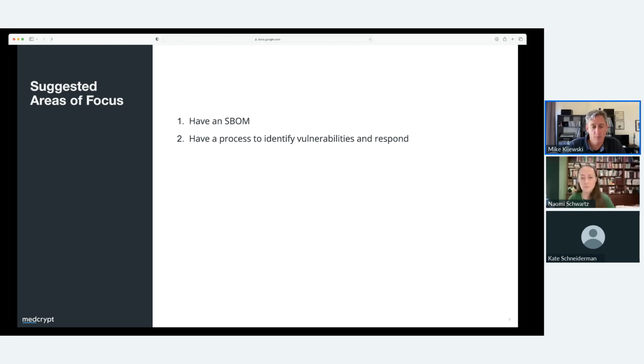You should do that. But you also need a process by which, if a new vulnerability is found 1 month after the release of your software, you're notified of that, and you have a process by which you determine, does this new vulnerability necessitate an urgent software update? Does it necessitate being addressed in the next planned software update, or is it not relevant to us? You need some process to do that.